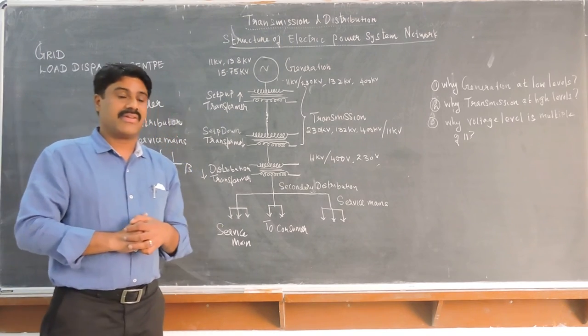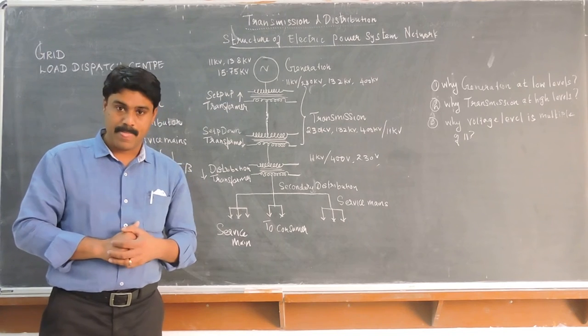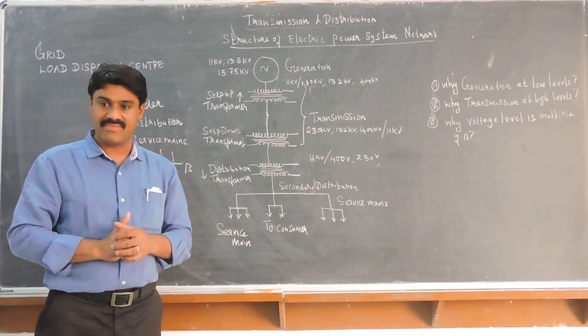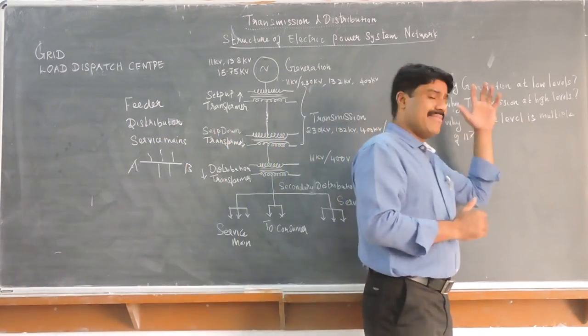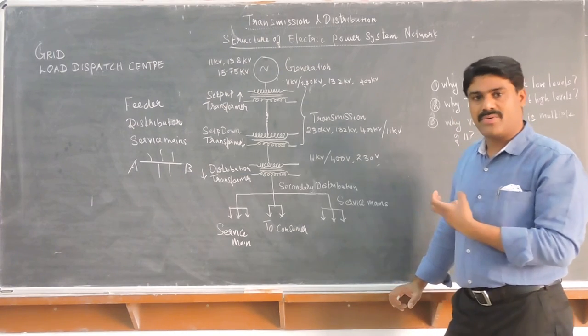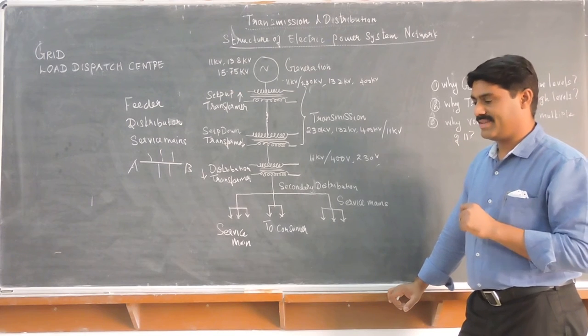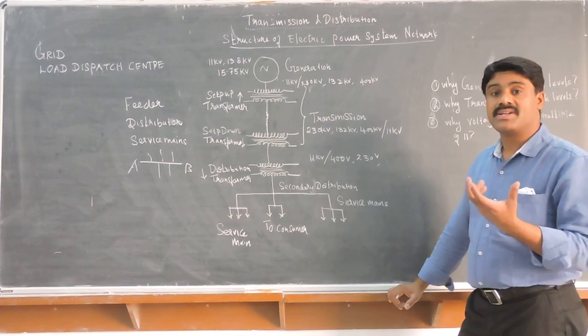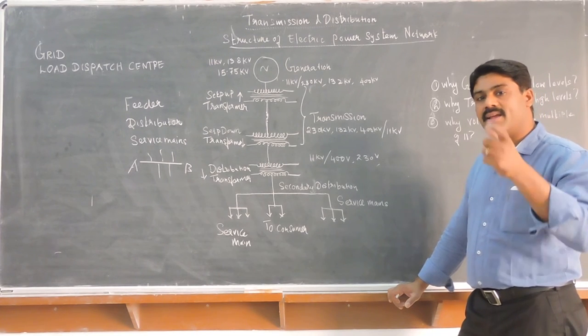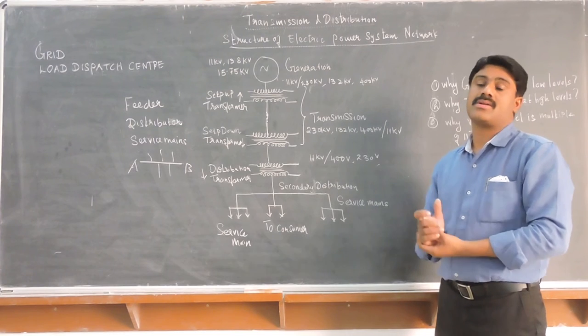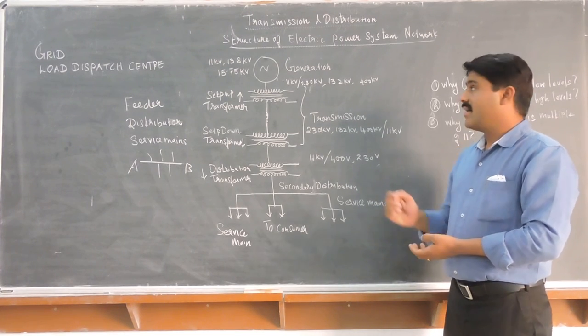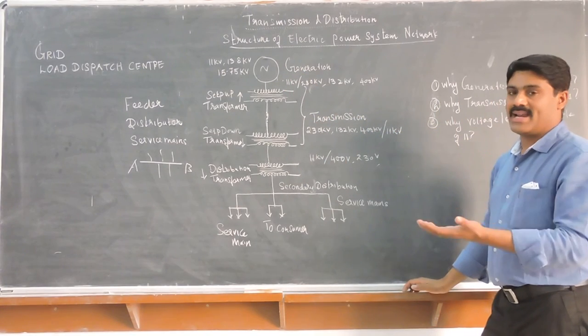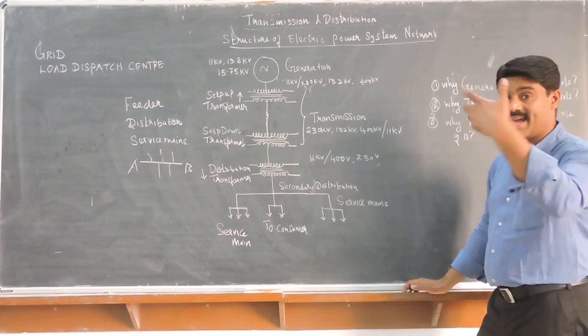In the last video, I asked why we go for low-level generation and why we maintain voltage over multiples of certain levels. Here is the answer. There are many factors, but I will conclude with two main reasons. First, if you go for a higher level of voltage generation, then insulation is a very big problem. Insulating coils for a higher voltage level is not easy — it becomes a tedious problem. Therefore, insulation is the primary reason for keeping voltage generation at a lower level.